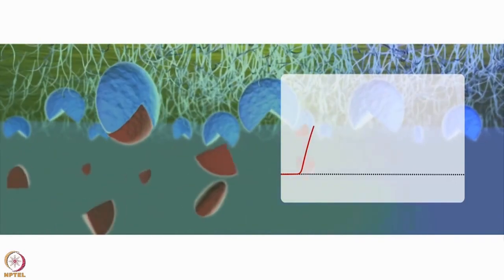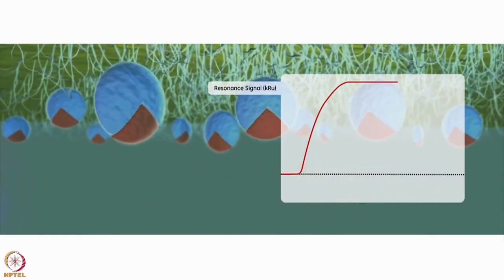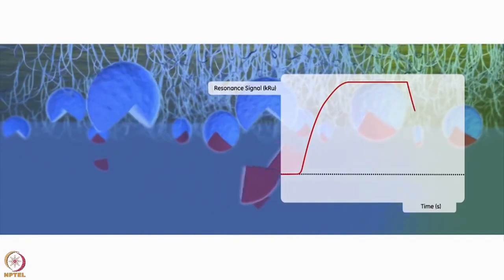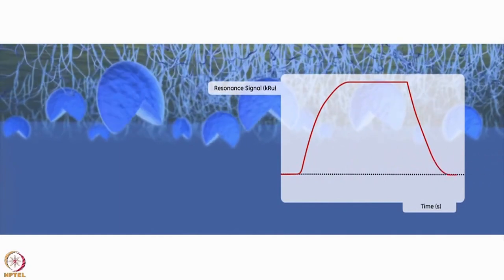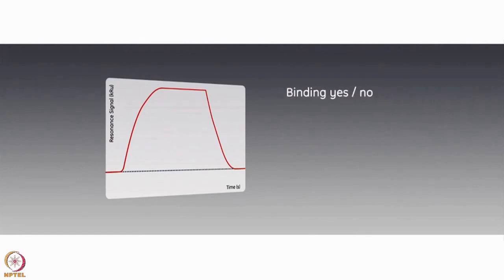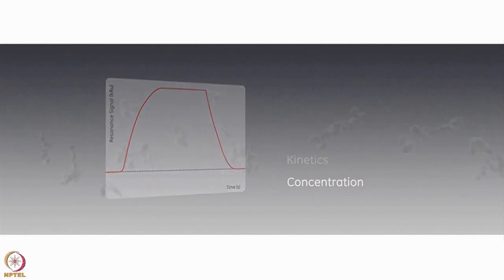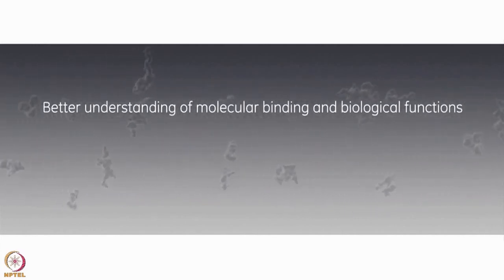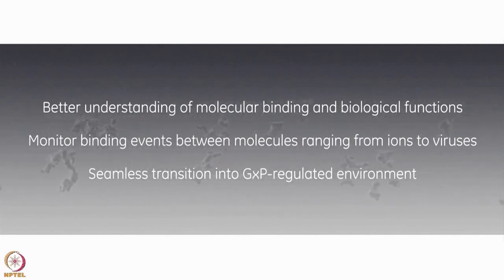The result from the detection of change in refractive index is displayed as a sensorgram, where the binding response on the y-axis is plotted against time on the x-axis. Since light does not penetrate the sample, analyses can be performed on colored, turbid, or opaque samples. From studying the shape of the sensorgram, binding yes or no, specificity, affinity, kinetics, and active binding concentration can be determined. The sensorgram provides real-time information about the entire interaction, giving a wealth of information about your binding — all without using labels.